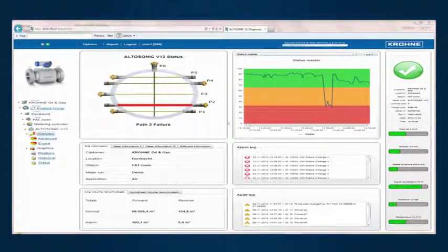There it is, we now get the full error on path 2. The meter is still custody transfer as it uses path substitution, so the other paths compensate for the failure of path 2. However, there is a failure on path 2, indicating you should warn your maintenance crew.